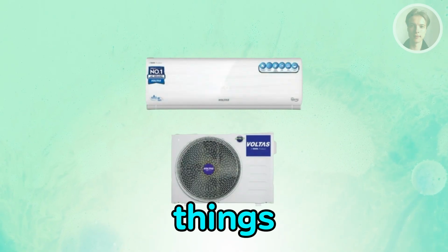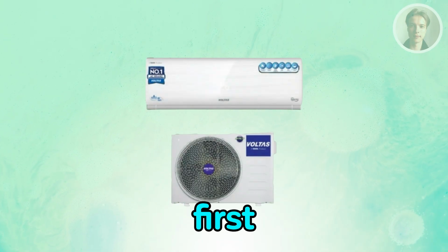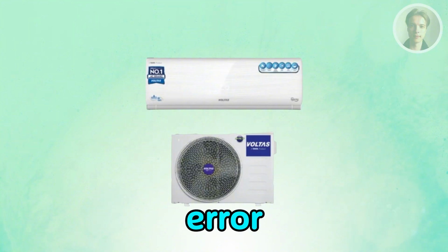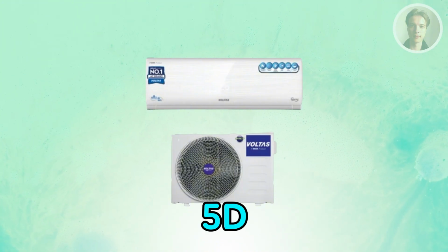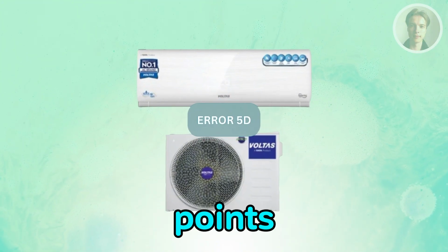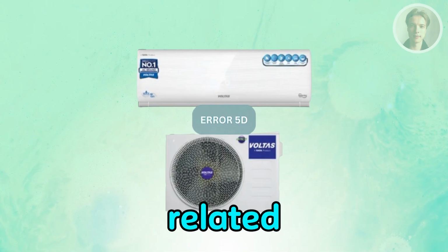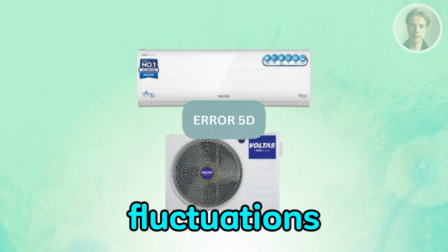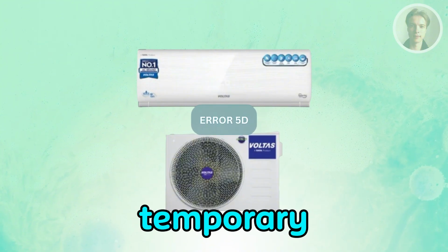So, if you want to fix the 5D error in your Voltas AC, there are a few things you may want to do here. First, you need to understand what the 5D error means. The error 5D on Voltas ACs usually points to a communication or sensor related issue, often triggered by power fluctuations, moisture, or a temporary control board glitch.